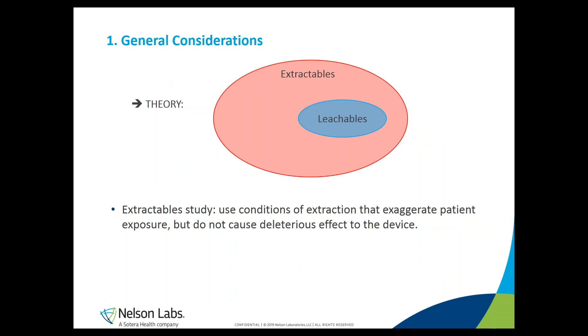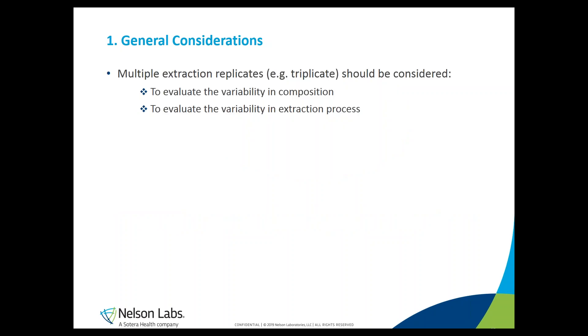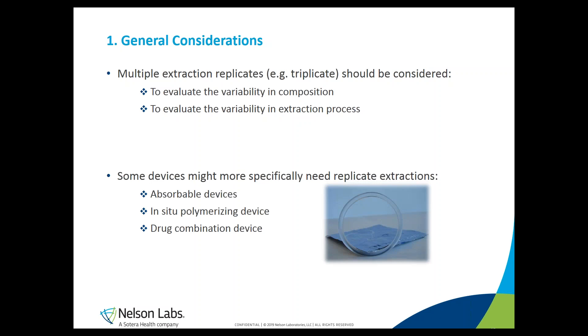In theory, leachables are a subset of extractables, and that is why if your medical device is already safe after extractable testing, you will not be required to perform a leachable study. In an extractable study, you use conditions that exaggerate patient exposure but do not cause deleterious effects to the device. The final draft also states that multiple extraction replicates such as triplicate testing should be considered, especially for absorbable devices, in situ polymerizing devices, and drug combination devices.